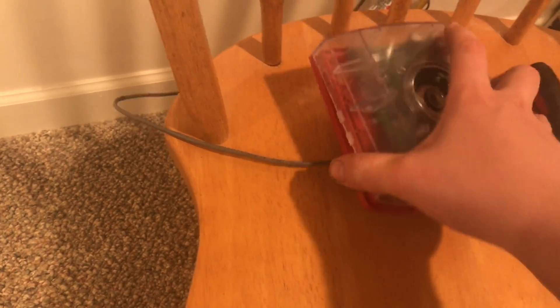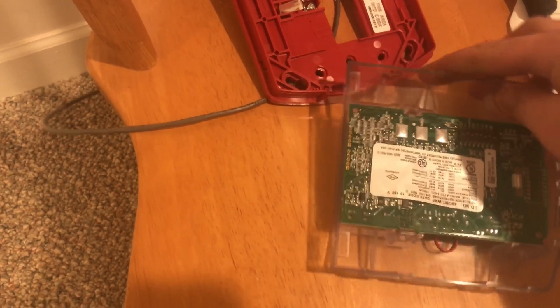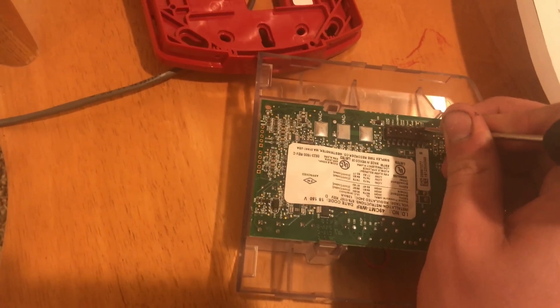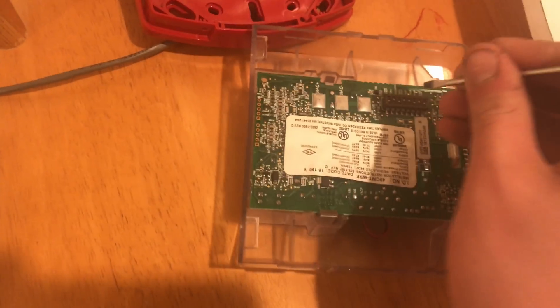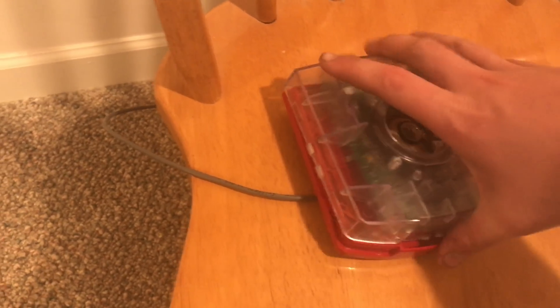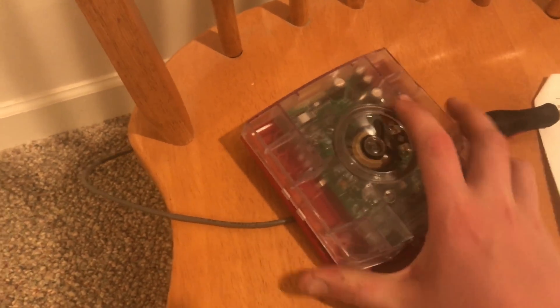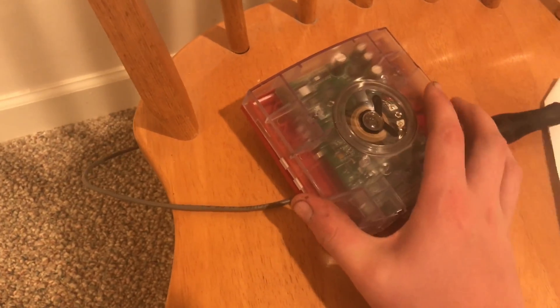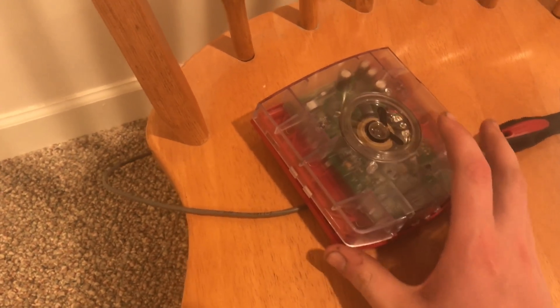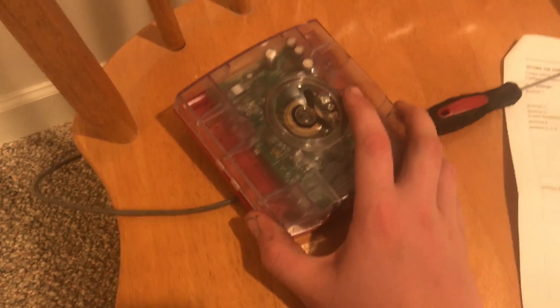That was siren. The next one is kind of cool — it's the 520 hertz. It can actually now function as a low frequency sounder, which is cool. So you can now have a low frequency sounder on your Simplex panel other than using a speaker sounder system. That was bell — I must have flipped the switch accidentally, so this is bell.